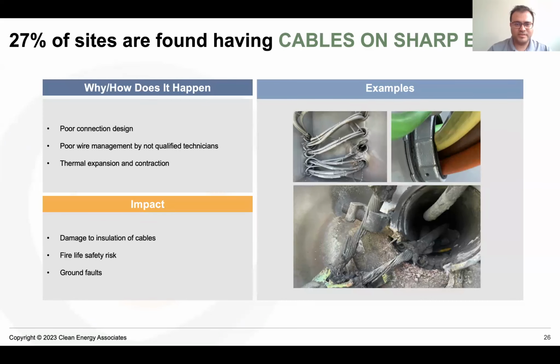We've found this issue on 27% of our sites, roughly 27 out of every 100 we inspect. This happens due to poor wire management by unqualified technicians and lack of oversight during construction. When the O&M team goes on site, they fix issues that are already wrong, but most of the time they don't inspect the sites for safety, and they don't realize something is wrong until it actually goes wrong.